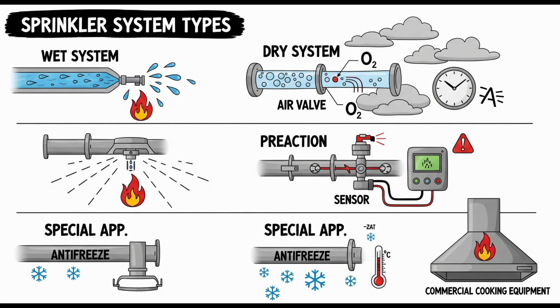Right. And these trapped air pockets can cause several problems. They reduce the volume available for water, potentially slowing down initial flow to a sprinkler head. Which you don't want. No. And over time, trapped air contributes to corrosion inside the pipe when in contact with water. Ah, corrosion. That makes sense. So a single air vent, typically located at a high point on the system, allows this trapped air to escape as the system is filled or repressurized. It ensures the pipes are completely full of water for optimal performance and longevity, and helps mitigate internal corrosion.